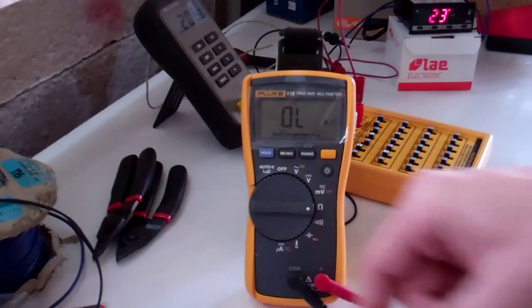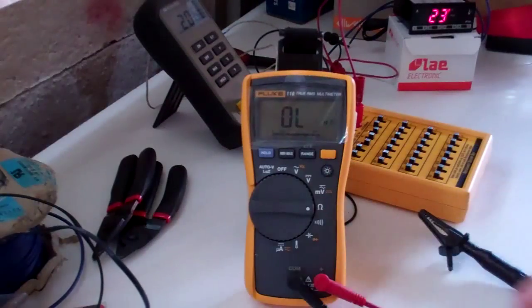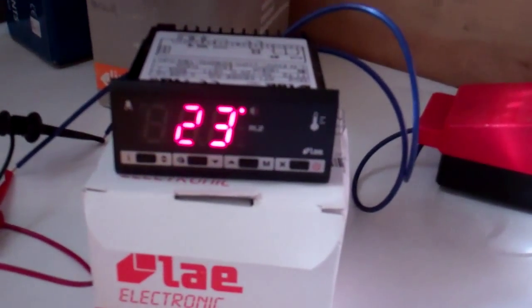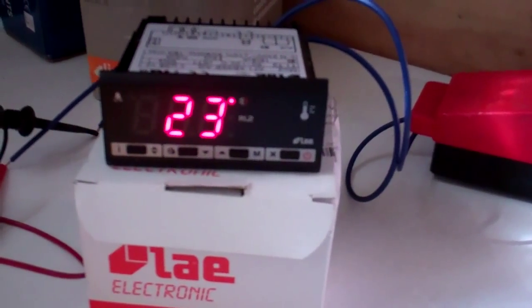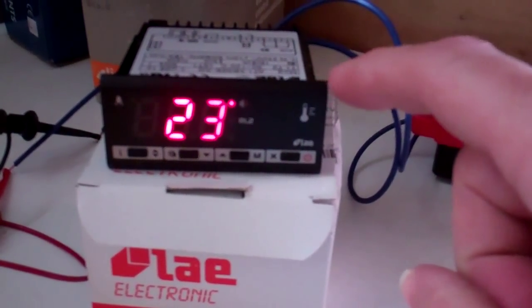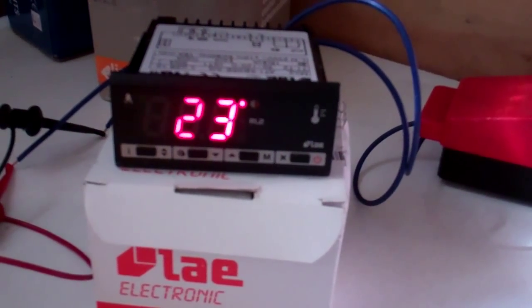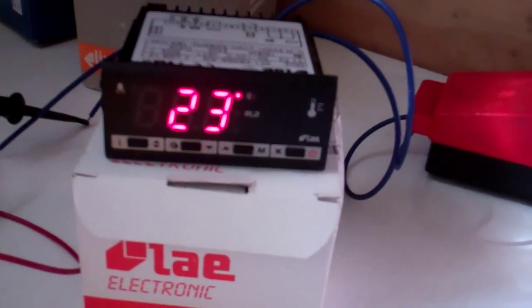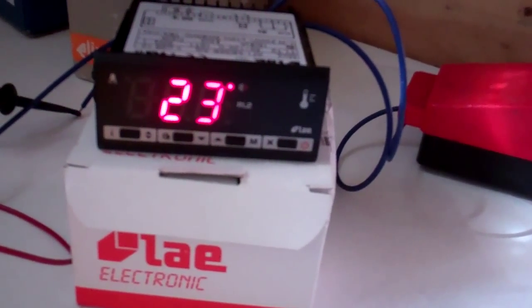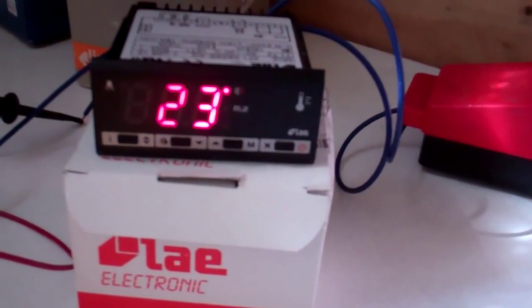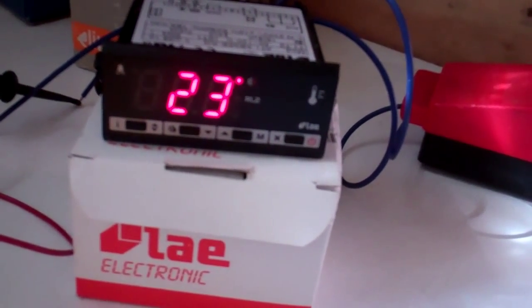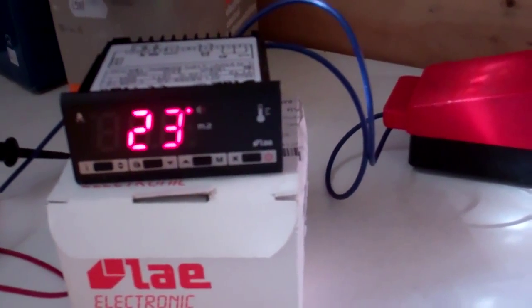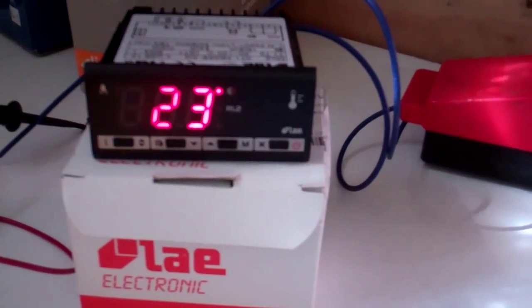One of the things when you get one of these displays reading the wrong temperatures, you never know whether it's the probe that's gone out. I mean that's most likely. Or whether it's the controller itself. Again if you knew that the, say 20 kohms it should read a set temperature, you could put this little box on there. Set it to 20 kohms and if the temperature was different you would then maybe think the problem might lie in the controller rather than the probes.